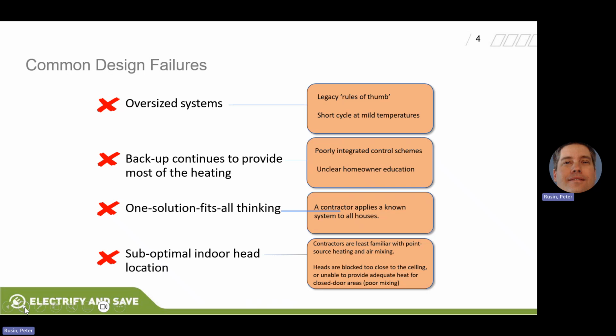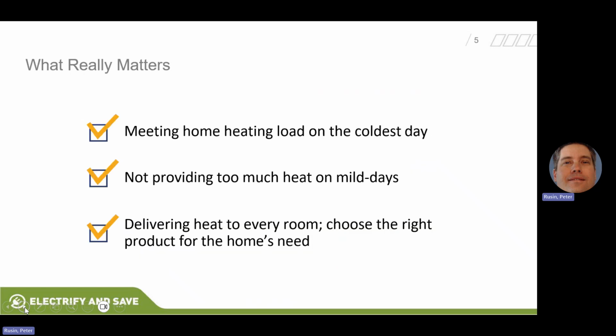One thing that's kind of a weird one - we see some indoor head locations placed too high, too close to the ceiling, where we're not really able to mix the air. You don't want to put them so high in the ceiling; you want to put them where they can mix the air. Also, we sometimes see one head serving an entire home - when bedroom doors get closed, air won't go in there. So we'll show you a couple drawings on that. But these are the design failures we typically see.